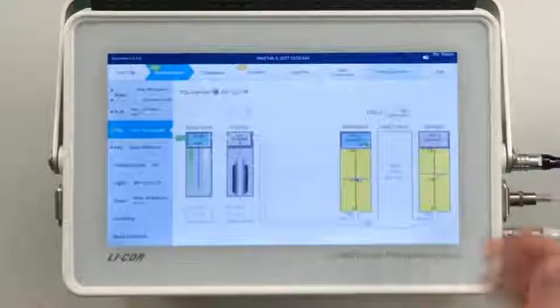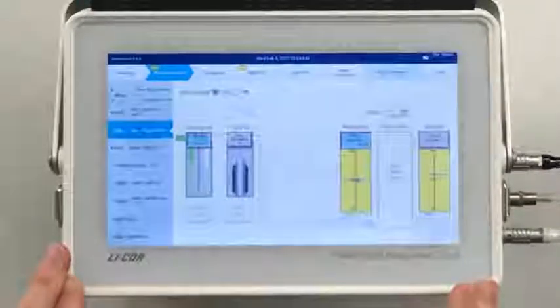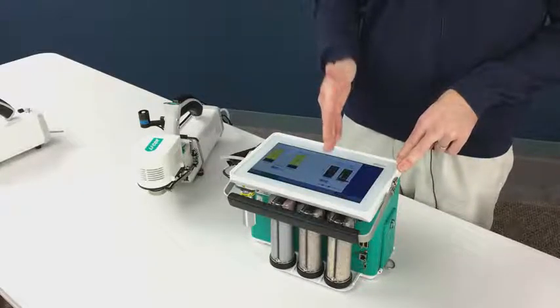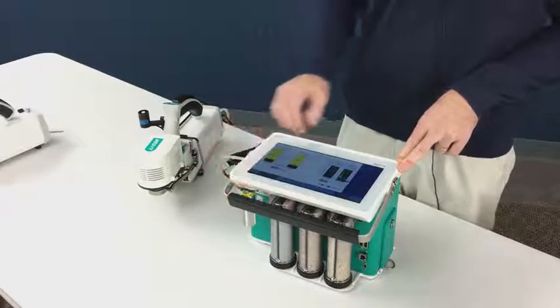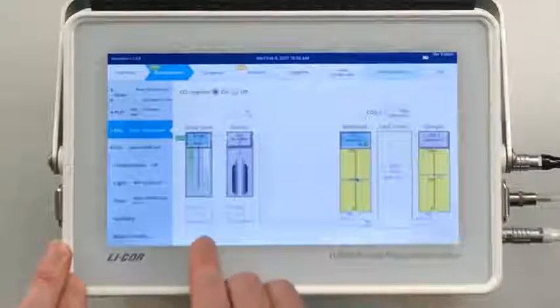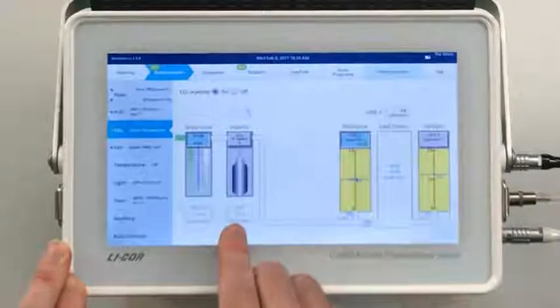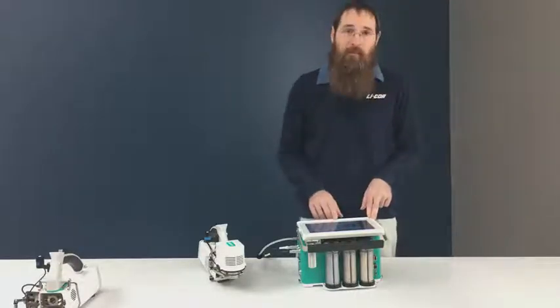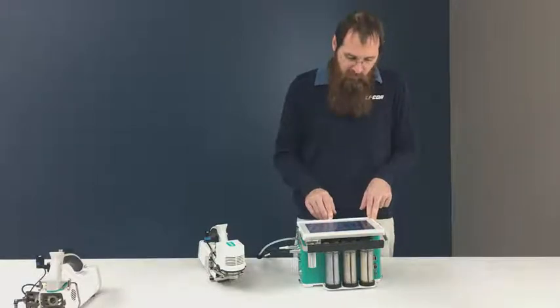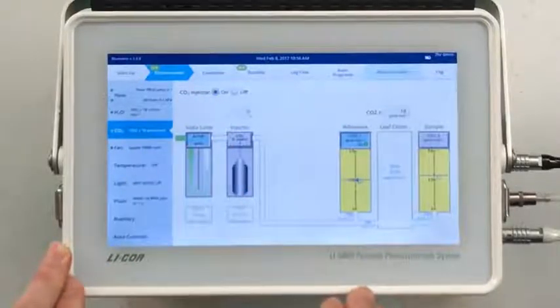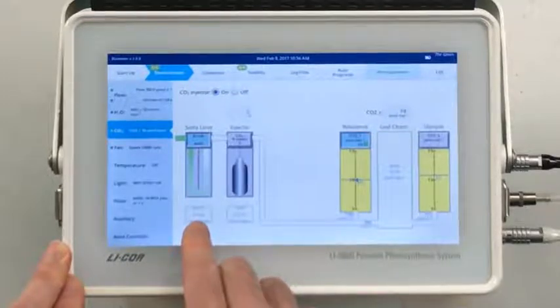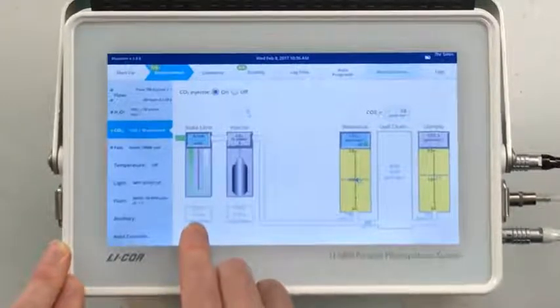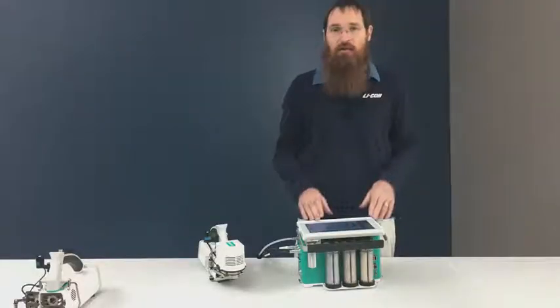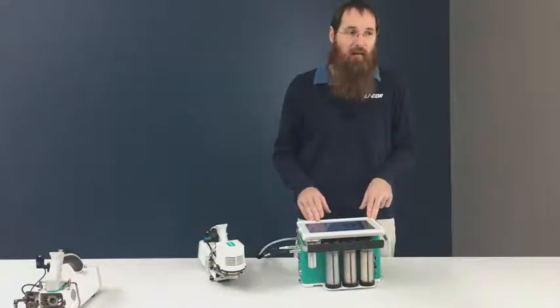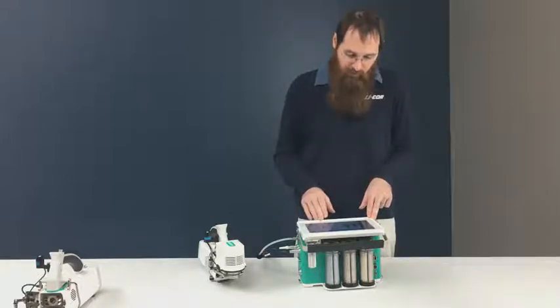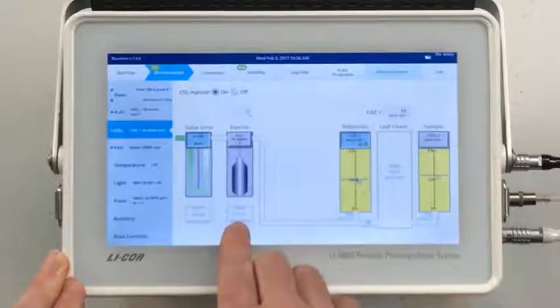CO2 control works much the same way, right? We have another diagram. This diagram updates in real time to show us what's happening. We have our soda lime column and we have our CO2 source, with our CO2 cylinder in it. We have counters at the bottom, right? If I fill my column up with fresh soda lime and I tap this little counter, it's going to compute over the runtime of the column how much CO2 it's absorbing. And so you have a metric on the instrument to quantitatively tell you as you're approaching exhaustion of the soda lime. And then the same deal with the CO2 source.